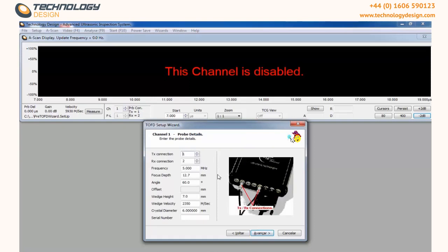Inform to which inputs your probes are connected to, the frequency, the focus depth, the angle of your wedges, the wedge height, the wedge velocity, and the crystal diameter.